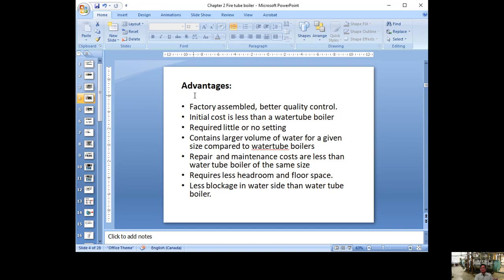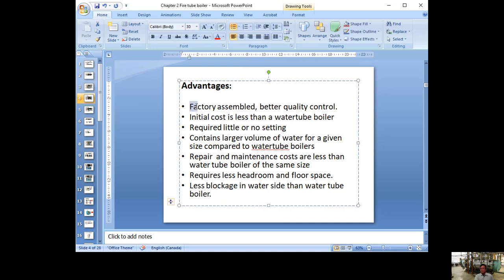Another advantage: because fire tube boilers are small in size, they are manufactured in a factory with better quality control, and the initial cost is much less than a water tube boiler. The main cost saving is because every tube is straight — you don't need much welding. You just put the tube into the tube sheet and expand it. No complicated bending like in water tube boilers with their mud drum and steam drum connections. They also require little or no special setting or support.